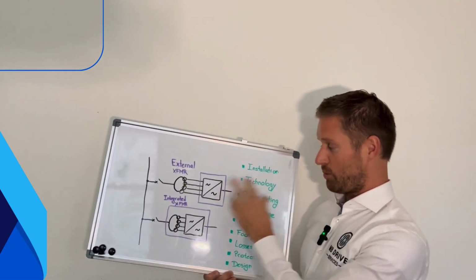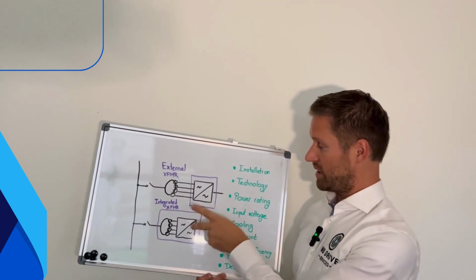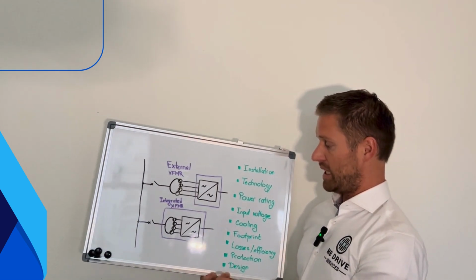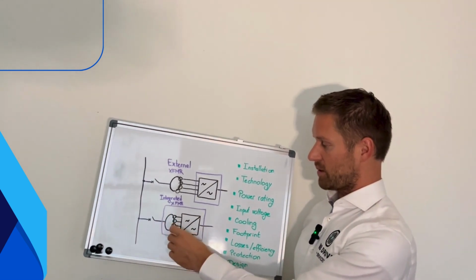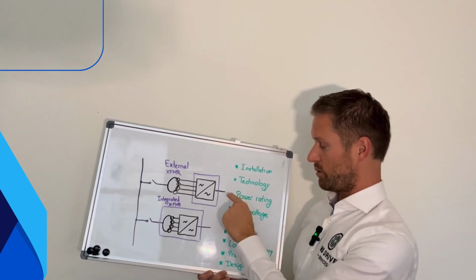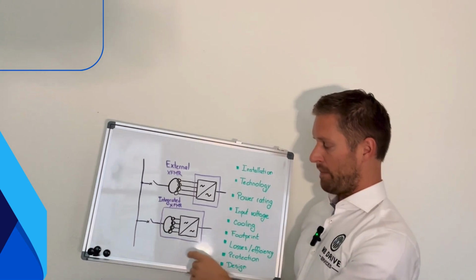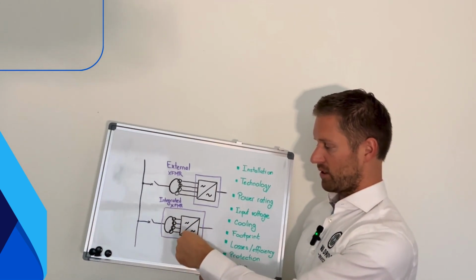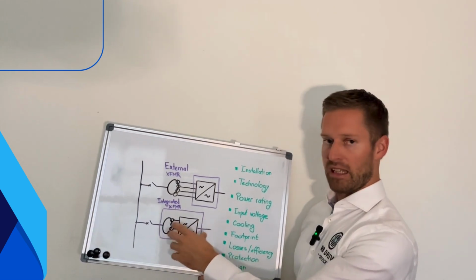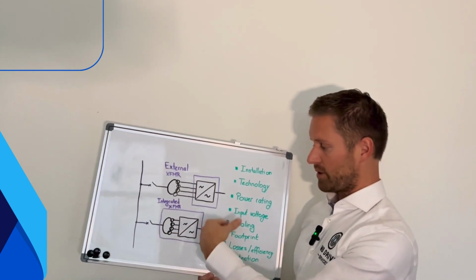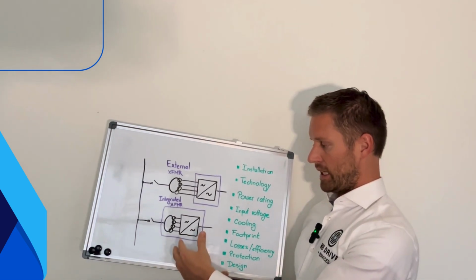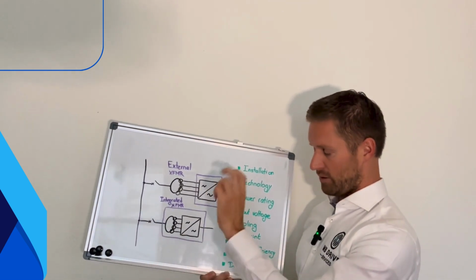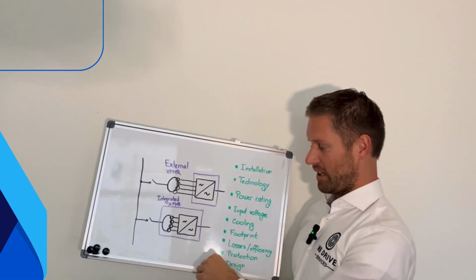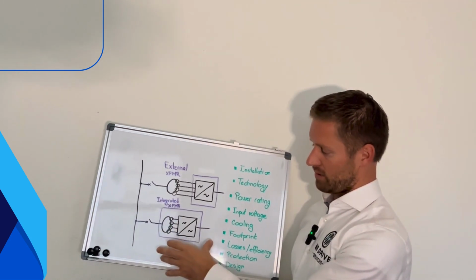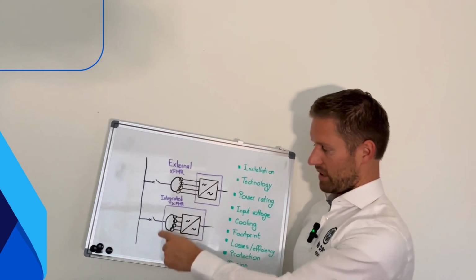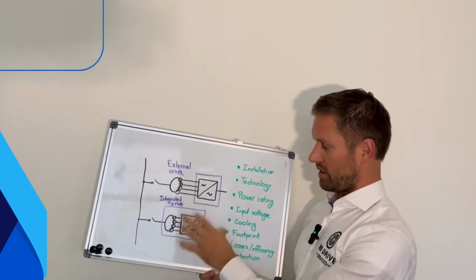So this is a very brief comparison of the two solutions. You see that there are quite some differences. We can summarize that the integrated transformer is more limited with regards to power rating, input voltage, and so on. On the other hand, it comes with all the internal connections between the transformer and VFD. This is all done already in the factory, so the installation is also easier. It's this kind of 3 cables in, 3 cables out concept. So for the end user, it's very convenient, but it's typically restricted to a lower power range and it has some limitations.